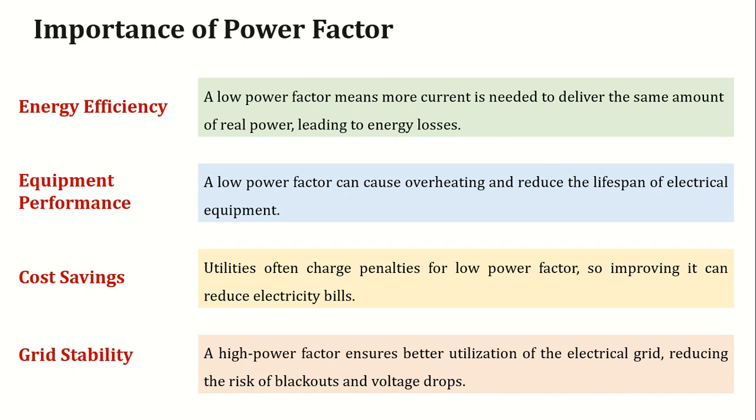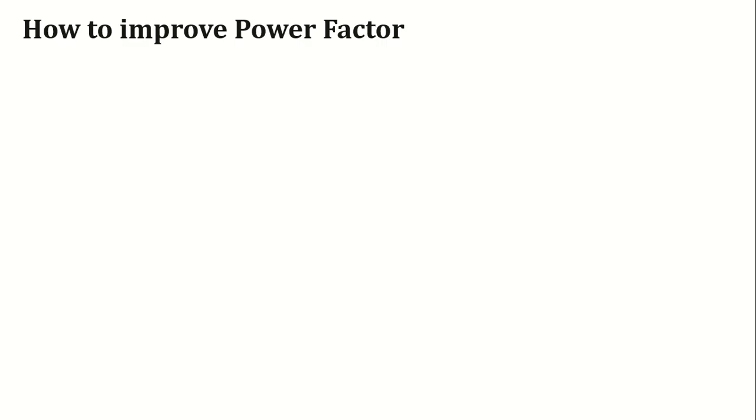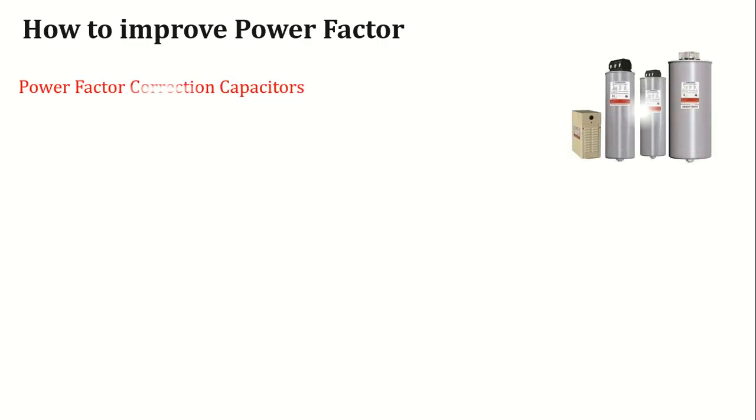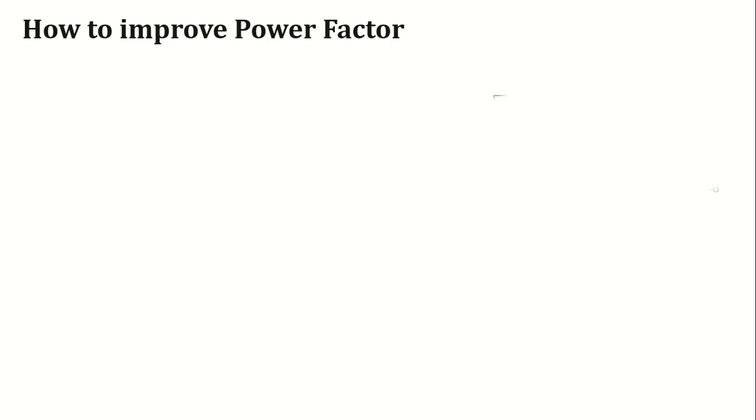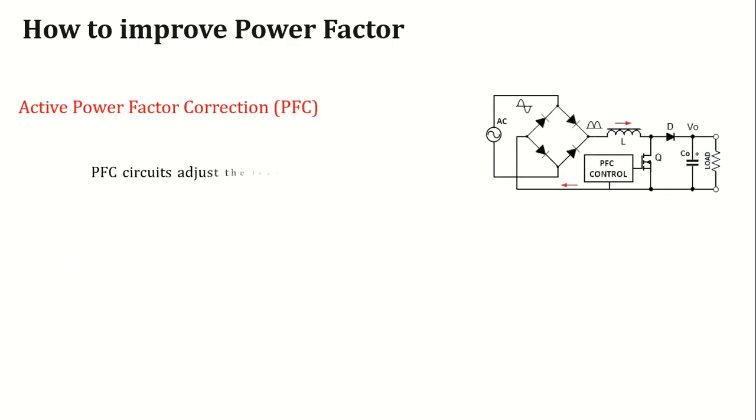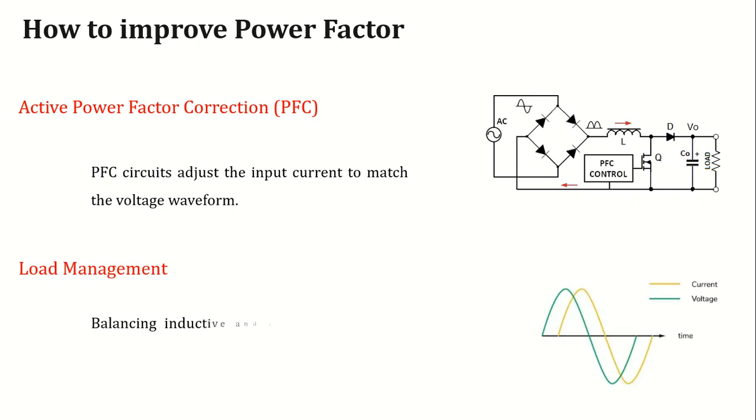Next I will shortly discuss the techniques to improve power factor, resulting in increased efficiency and cost savings. The first way is to use power factor correction capacitors. Capacitors are added to the system to counteract the lagging power factor. Next comes synchronous condensers. These are rotating machines that provide reactive power to improve power factor. At number three comes active power factor correction PFC. Used in electronic devices, PFC circuits adjust the input current to match the voltage waveform. The last we can do is proper load management. Balancing inductive and capacitive loads can help maintain a high power factor.